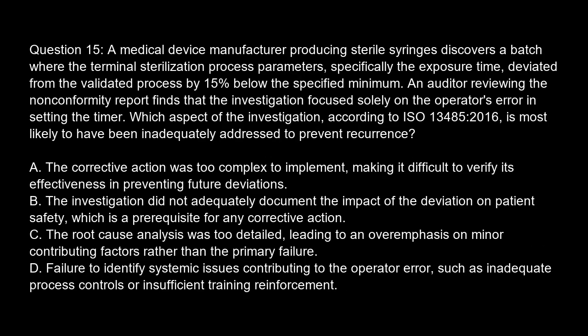Question 15. A medical device manufacturer producing sterile syringes discovers a batch where the terminal sterilization process parameters, specifically the exposure time, deviated from the validated process by 15% below the specified minimum. An auditor reviewing the nonconformity report finds that the investigation focused solely on the operator's error in setting the timer.